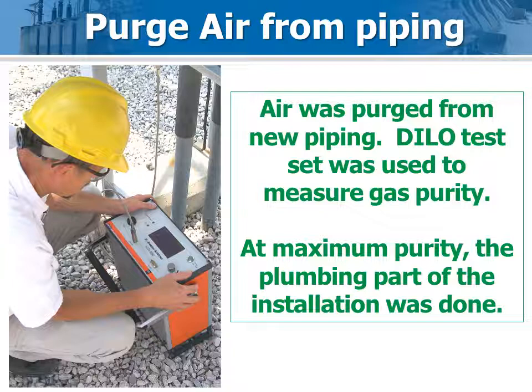The gas piping system was purged of air by connecting the new fill port to a gas purity analyzer. When the gas purity hit a maximum, the system was again checked for leaks. After the purity analyzer was disconnected, the breaker was topped up to nominal pressure from a gas handling cart.